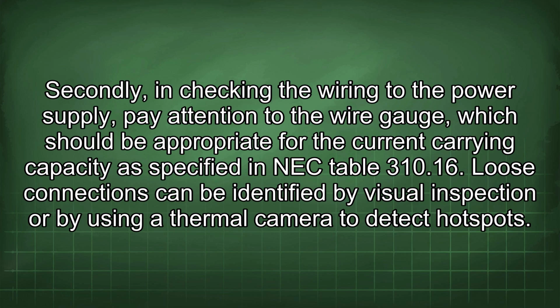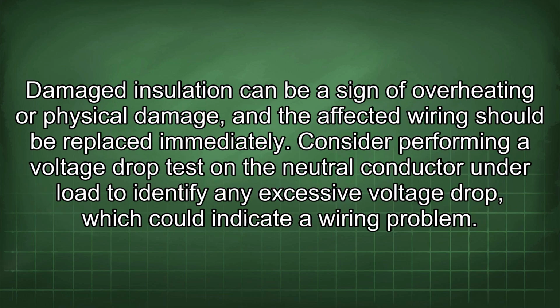Secondly, in checking the wiring to the power supply, pay attention to the wire gauge, which should be appropriate for the current carrying capacity as specified in NEC Table 310.16. Loose connections can be identified by visual inspection or by using a thermal camera to detect hotspots. Damaged insulation can be a sign of overheating or physical damage, and the affected wiring should be replaced immediately.